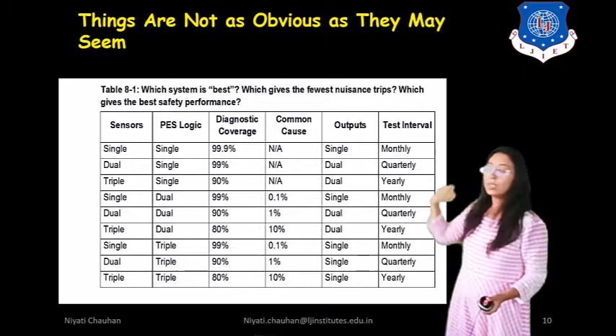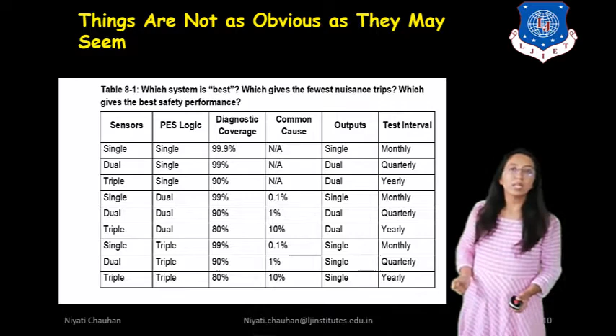Dual is not always better than simplex, and triple is not always better than dual. Here we are using two systems, then complexity will be increased, and instead of 2 we use 3, thereafter complexity will also be increased. Consider the 9 choices presented in table 8.1. In the next slide we will see table 8.1. Let's assume at this point that the 9 different cases shown in the table have a software-based logic system, programmable electronic system, PES. So here you can see 9 choices are available. In this chart we show which type of sensors we are using: single, dual, triple, then PES logic, then diagnostic coverage, then common cause, output, and test interval. We are testing this device monthly, quarterly, yearly.